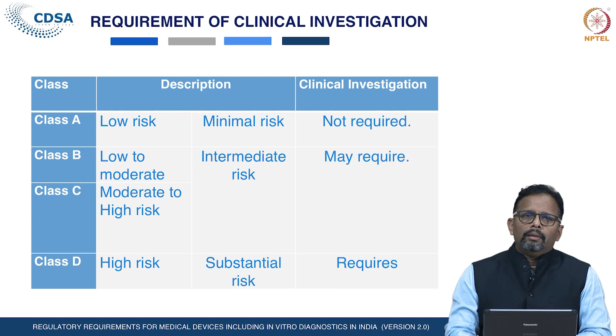And for the high risk medical devices, the clinical investigation is required to establish the safety and performance of the devices, and this clinical investigation is applicable only for the devices which fall under the definition of investigational medical devices. For devices other than the investigational devices, it is not mandatory to carry out clinical investigation, as the safety, performance and efficacy have already been established. So, for high risk devices and intermediate risk devices, there is a requirement of clinical investigation, and for low risk devices like class A devices, there is no requirement of clinical investigation.